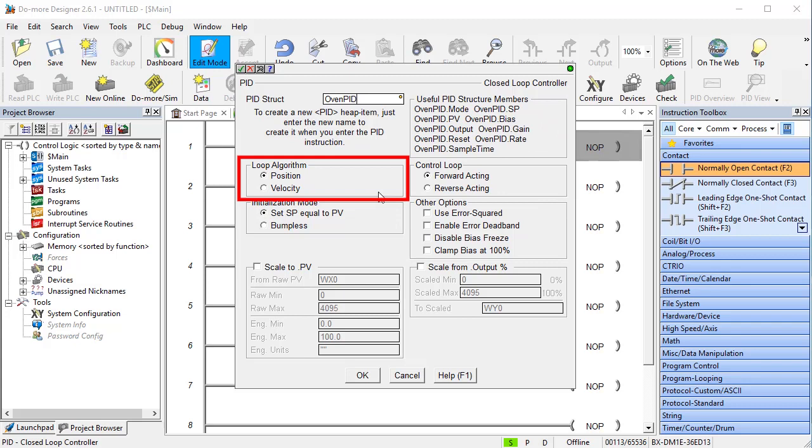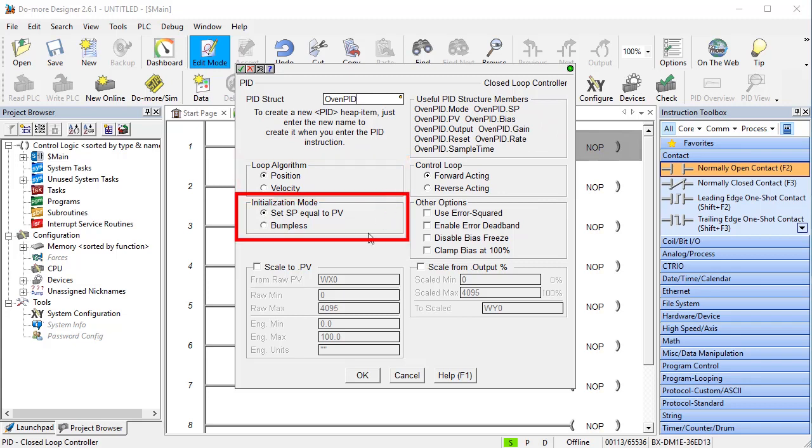Well, if you are measuring the amount of speed, not how fast it is changing, then it is still a position algorithm. That does trip up a lot of people, so be careful about which one you choose here. This tells PID that when it first starts, it should set the setpoint at whatever level the process is currently at. That's to prevent sudden changes when PID starts. In our temperature example, that won't be a big deal, so we'll come back to this initialization stuff in other videos.